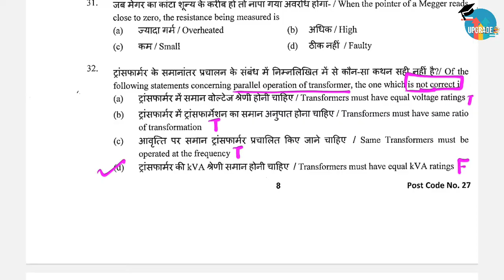Next question concerns parallel operation of transformers: which of the following statements is not correct? Transformers must have equal voltage rating - true. Transformers must have the same ratio of transformation - true. Transformers must be operated at the same frequency - true. Transformers must have equal kVA ratings - not true. So the correct option is D, during parallel operation of transformers it is not necessary that both transformers have the same kVA ratings.